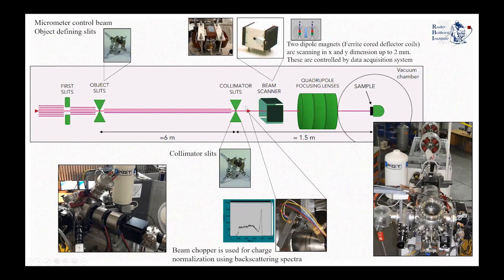After this chopper, the beam enters the beam scanner. This is composed of two dipole magnets, called deflector coils, which scan the beam in x and y dimensions. They can give us a scan distance of up to two millimeters and are controlled by the data acquisition system. Then the beam enters the quadrupole system and finally enters the microprobe chamber.